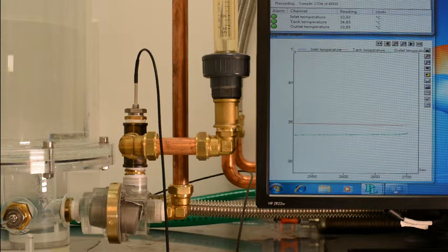So the inlet temperature is now slowly starting to increase. And the temperature inlet is now 34.31, while the tank temperature is 34.84. So we're now at half a degree lower than the tank temperature, and the closure is still complete. You can also see from the valve it's still in the bypass position, and right about now the temperature of the inlet and the tank are the same.